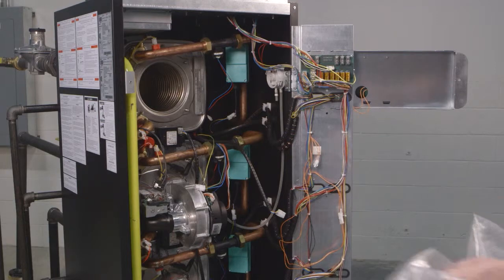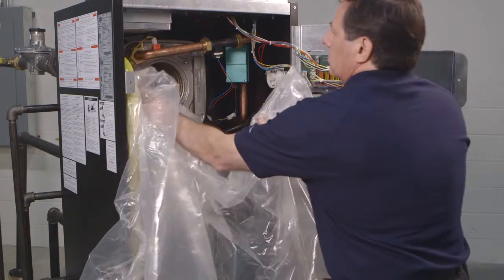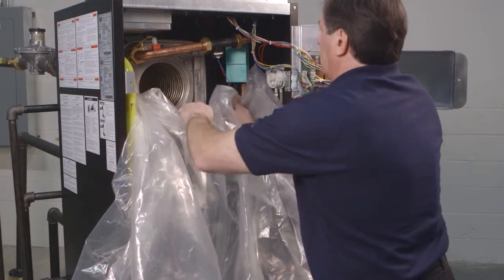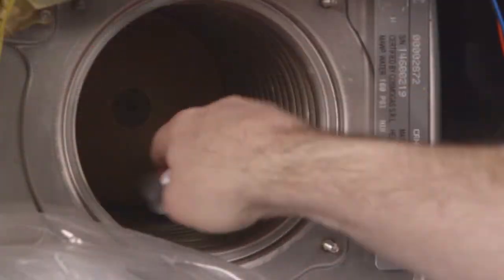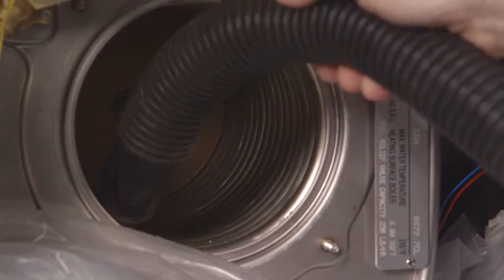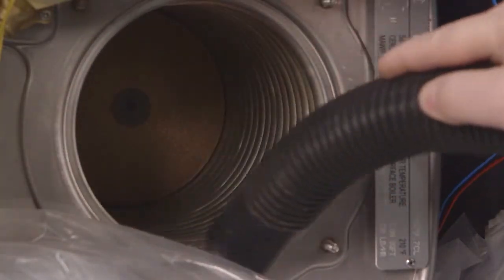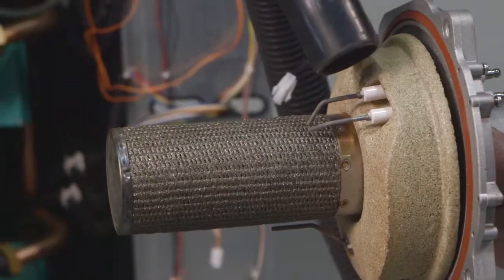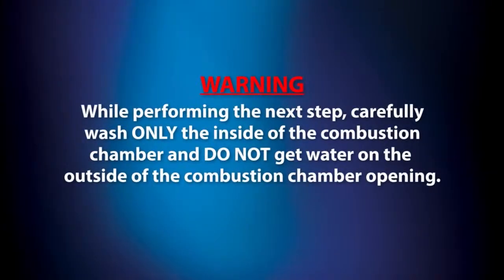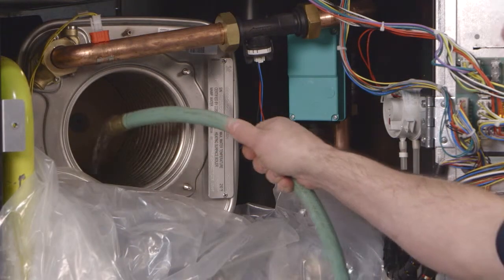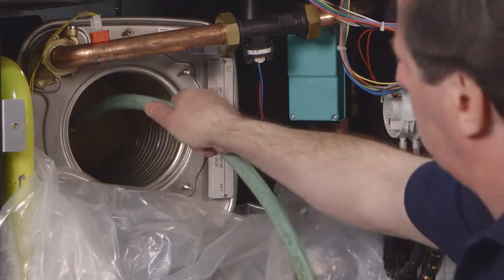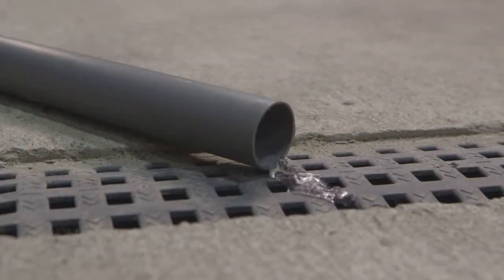Prepare a suitable cover for the burner so that no dirt, water, or other foreign objects can fall into the burner unit from above. Use a brush with plastic bristles to clean the inside of the combustion chamber. Use a vacuum cleaner to remove any unburned residue from the combustion chamber. Clean the surfaces of the burner and around the electrodes using the vacuum cleaner. While performing the next step, carefully wash only the inside of the combustion chamber and do not get water on the outside of the combustion chamber opening. Using only water, wash the inside of the combustion chamber. The water will drain into the condensate drain as depicted here.